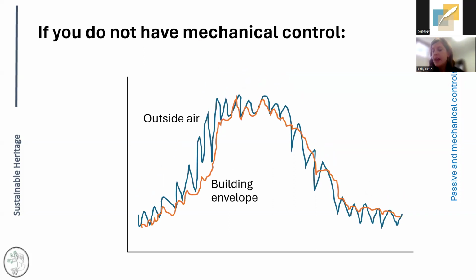And yeah, you just generally see this more buffered version, but it's still following the same trends, especially over longer periods of time. And if this is what you're seeing, your general goal is going to be that you want to reduce sources of added moisture. You don't have the mechanical means, so that building envelope is that outermost level of the levels of control that you can use to impact your dew point. So you want to stop as much moisture as possible from coming in the summer.